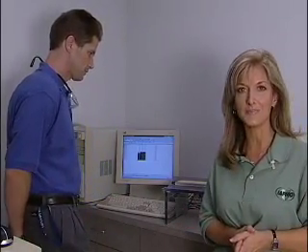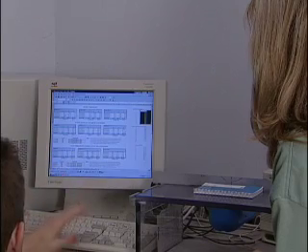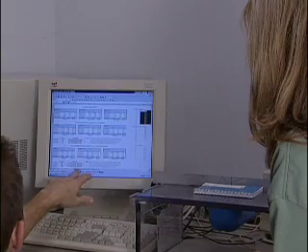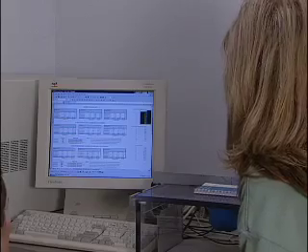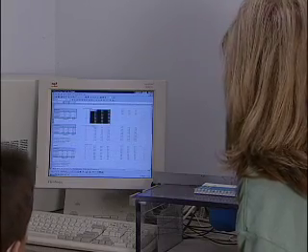Even through the 2-inch glass, you can feel the heat that emanates from the light inside. A colorimeter determines color change after accelerated aging. After testing in the Xenon Arc Accelerated Aging Unit, plastics are examined in this machine, which measures the difference between the aged and unaged samples. Variations are measured along the color spectrum to determine how much the plastic has faded.